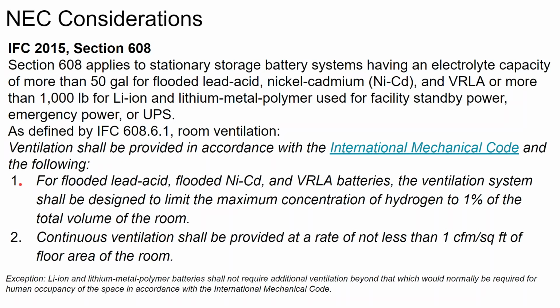But the other part of code is a little bit harder to meet for IFC. They say, well, it's not just that you have a ventilation system that clicks on every 30 minutes and blows the air out of the room and prevents that hydrogen gas from accumulating in amounts greater than 1%. What we also need is a minimum amount of continuous ventilation. And that is what an air conditioning unit is not going to do, provide continuous ventilation. Well, maybe some variable speed air conditioners will. But this is where it says, shall be provided at a rate of not less than 1 cubic foot per minute per square foot of the floor area of the room.